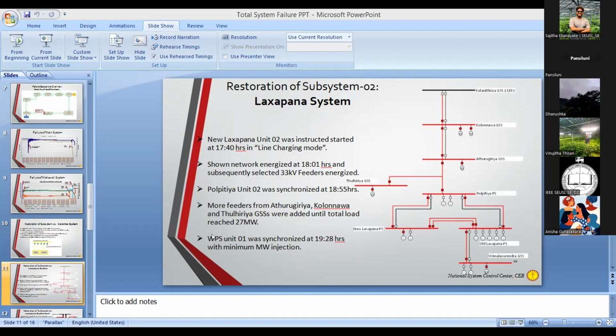The third machine, WPS unit 01, has been synchronized at 19:28. This much time is taken because the machine has to be loaded gradually, not like in normal operation. Because of less inertia, they have to do it very slowly. That is why during a total failure it takes some time, sometimes more, right? Somewhere around 4 to 5 hours to energize the whole system. So that is about the Laxapana system.